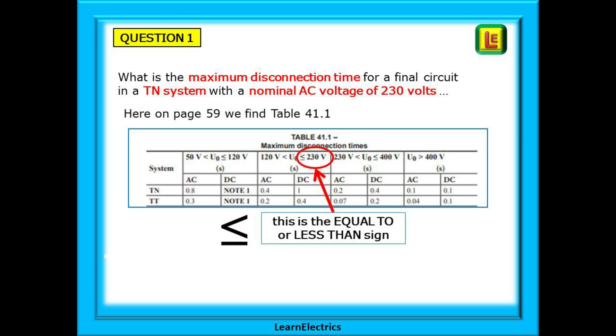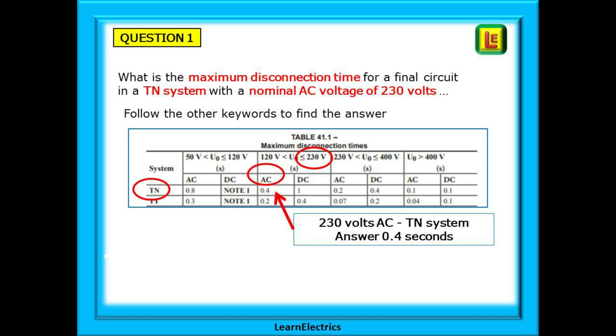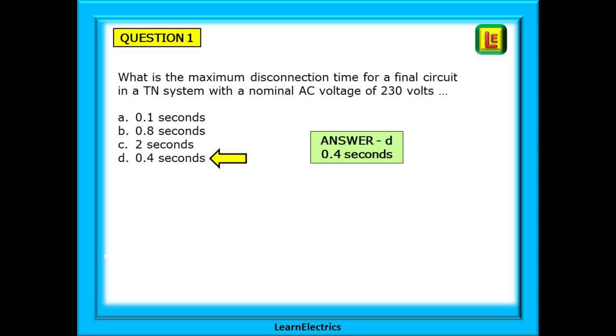Here is Table 41.1 and we can start to use our other keywords. You need to get used to this symbol — it looks like a letter V on its side with an extra line. This symbol says 'equal to or less than'. The nominal voltage must be equal to or less than 230 volts. This is nominal voltage, even though the actual voltage may be 240 volts or more. For any domestic final circuit, always assume 230 volts nominal. If we follow the keywords, we will see that we have an AC column and a TN row. Where they cross is our answer, and we should select choice D, 0.4 seconds.